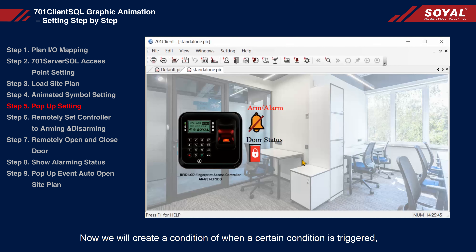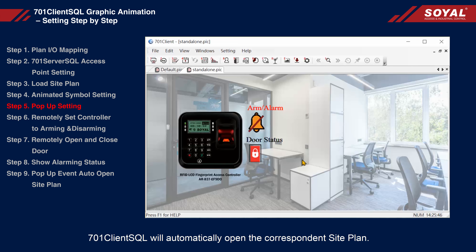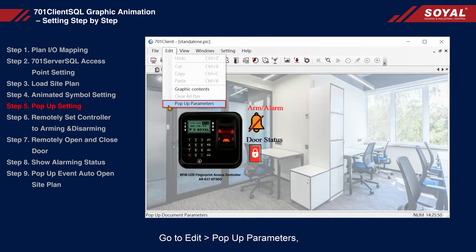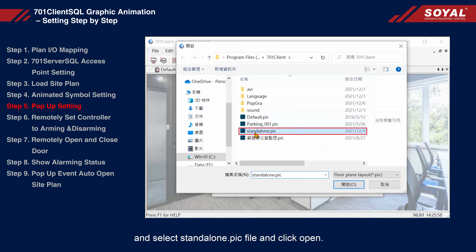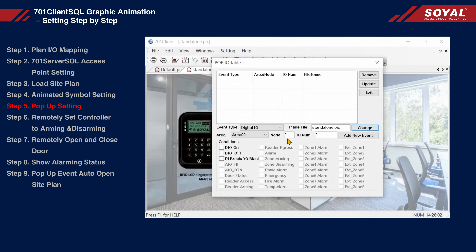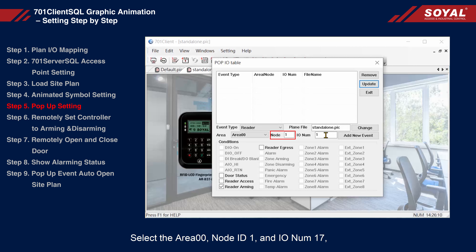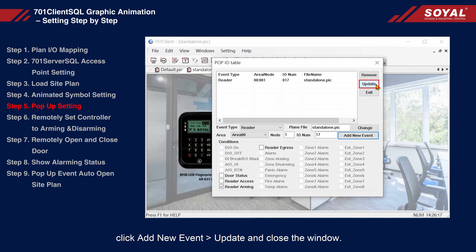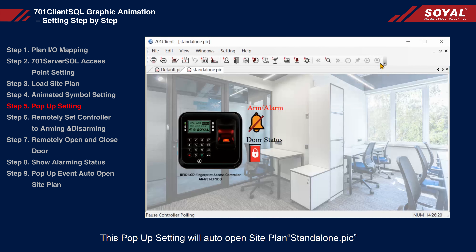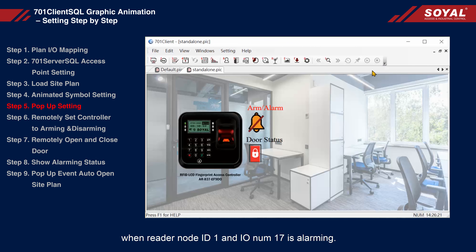Step 5: Pop-up setting. Now we will create a condition where, when a certain condition is triggered, 701 client SQL will automatically open the corresponding site plan. Go to Edit and select Pop-up Parameters. Change the plan file by clicking Change, and select the standalone PIC file, and click Open. Select event type Reader and tick Reader Arming. Select area 00, node ID 1, and I/O number 17. Click Add New Event, Update, and close the window. This pop-up setting will auto-open the site plan 'standalone PIC' when reader node ID 1 and I/O number 17 is alarming.